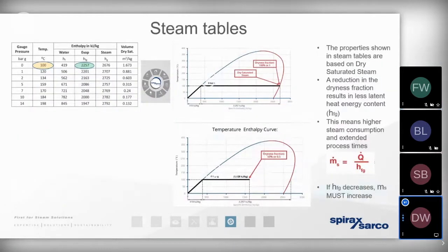So another thing we need to give thought to is how dry the steam is. That really emphasizes how critically important that separator is. We know that wet steam results in mechanical issues such as erosion, corrosion, water hammer. But if we fail to put the full amount of energy into the steam to make it evaporate to produce dry saturated steam, we're going to end up with wet steam. And as we can see from the temperature enthalpy curve, that wet steam is going to have less energy contained within it. So you can appreciate that with wet steam, the process time is going to extend and extend.